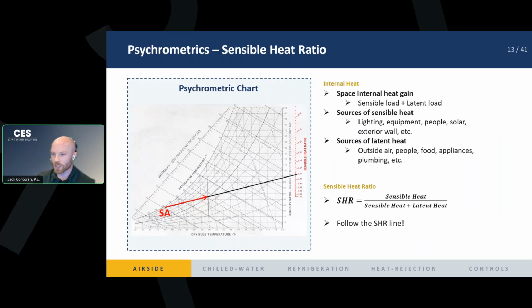So if you don't have any heating or cooling in the space and your sensible heat ratio is 0.7, your 75-degree air with 50% relative humidity is going to increase in temperature and increase in humidity at that ratio, right? And you can just find that along the line that you drew of your sensible heat ratio. And this equation is pretty powerful, right?